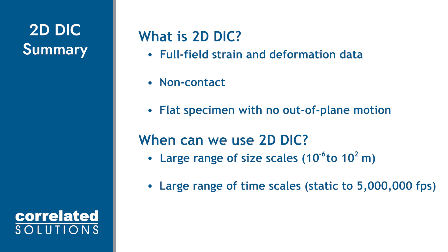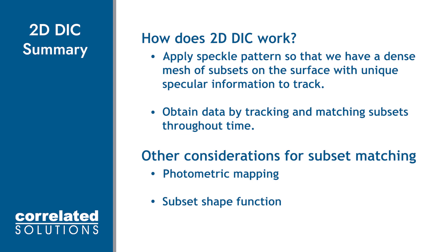In review, 2D DIC is a non-contact method that obtains local and global shape, deformation, and strain data. But with one camera, the specimen must be flat and not move towards or away from the camera. Depending on simply what lens and what camera is used, we can use 2D DIC on surfaces down to a millimeter in size or up to meters in size, from quasi-static applications up to millions of frames per second. DIC works by applying a speckle pattern so that we have a dense mesh of subsets on the surface with unique speckle information to track as the specimen deforms. We obtain data by tracking and matching subsets throughout time while accounting for changes in the subsets such as light changes or shape deformation.